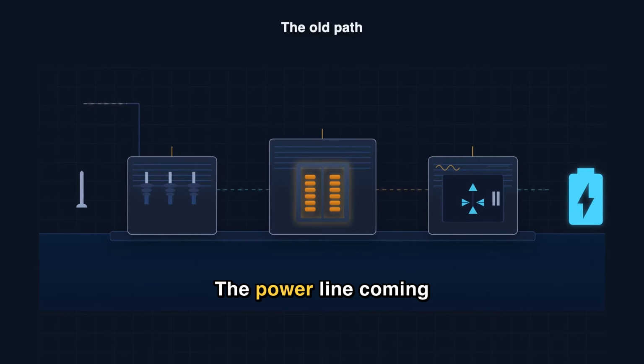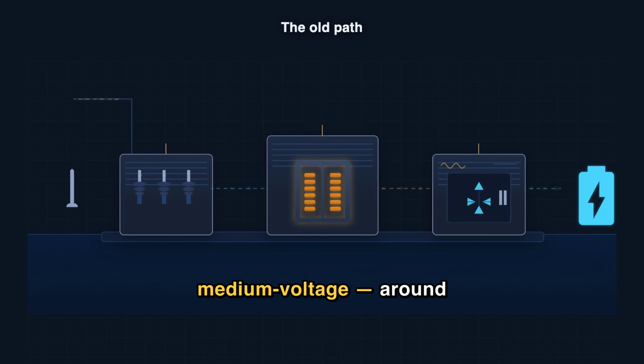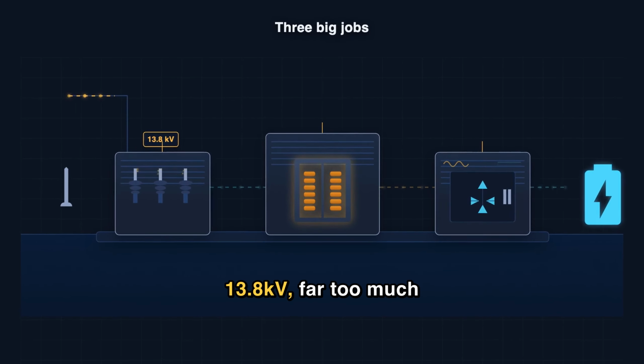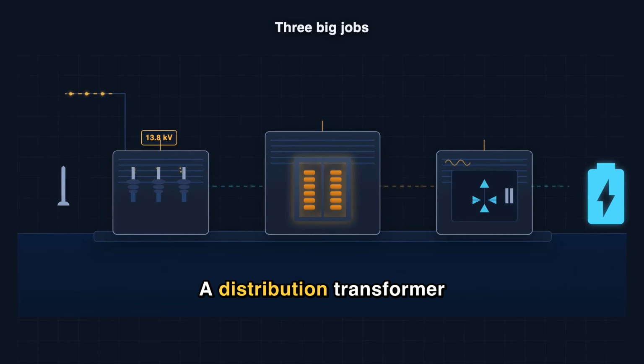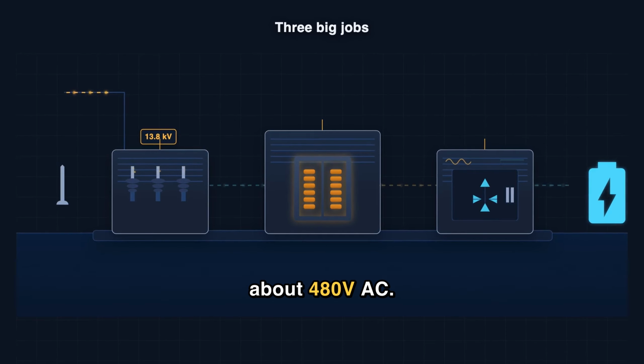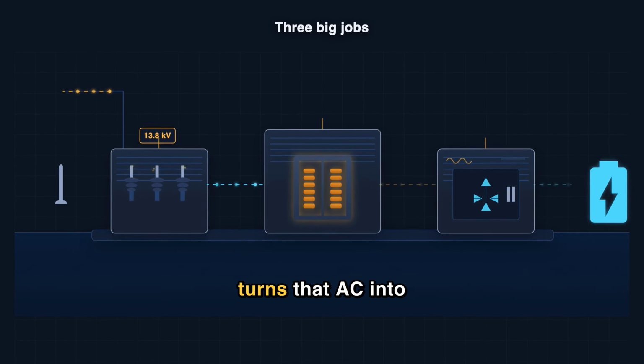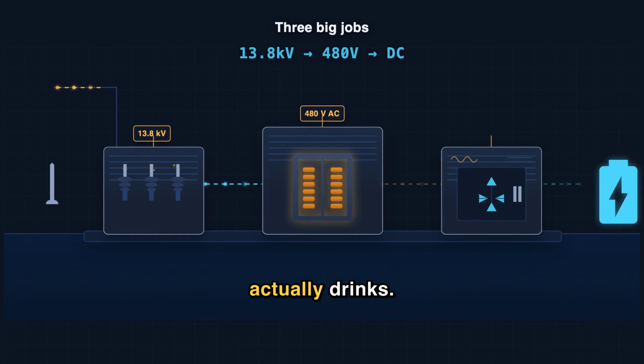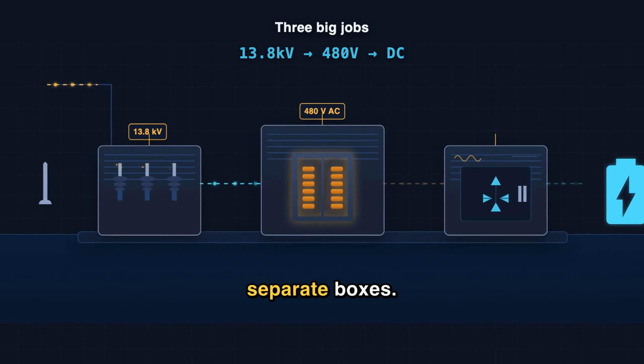Why? Start with the old path so the leap makes sense. The power line coming down your street is medium voltage, around 13.8 kilovolts, far too much for any car. A distribution transformer steps that down to about 480 volts AC. Then a separate rectifier turns that AC into the DC a battery actually drinks. Three big jobs, three separate boxes.